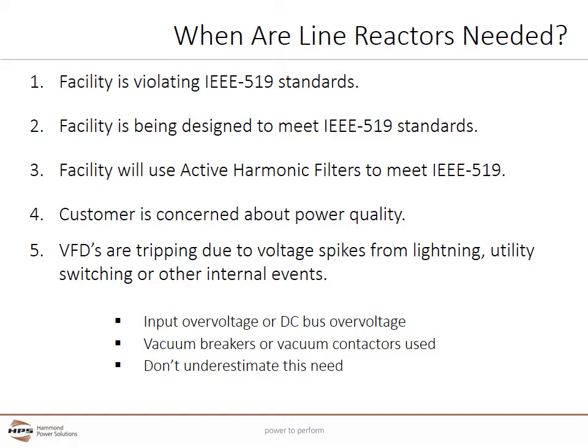Line Reactors should be considered whenever a customer is concerned about power quality. Line Reactors can help mitigate VFDs which are tripping due to voltage spikes from lightning, utility switching, or other internal events. This nuisance tripping shows up when input overvoltage or DC bus overvoltage faults occur.